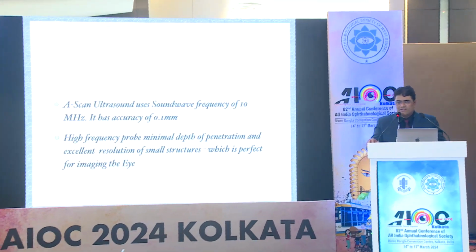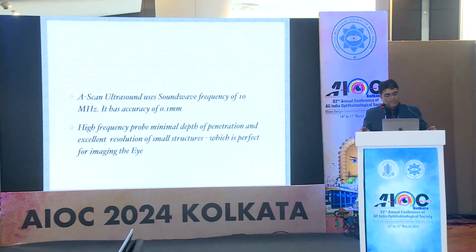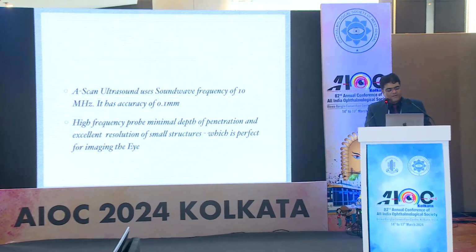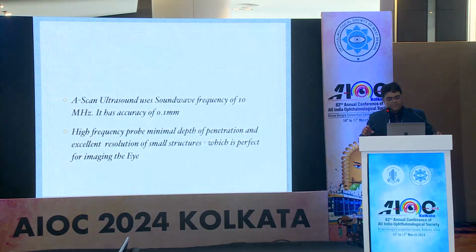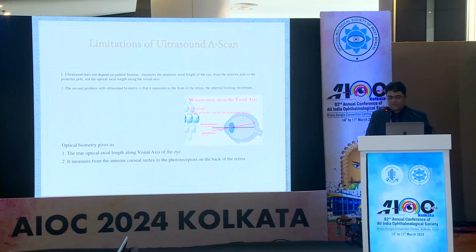So I'll be speaking on advances in optical biometry. Right. We all know that biometry is the practice of applying mathematics to biology. Broadly, biometry systems are either ultrasonic based or optical biometer based. A-scan ultrasound uses a sound wave frequency of 10 megahertz, which has an accuracy of only 0.1 millimeters. Why do we use this high frequency? Because it has minimal depth of penetration but excellent resolution for small ocular structures, which is better for the eye.